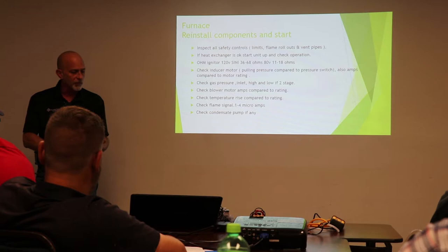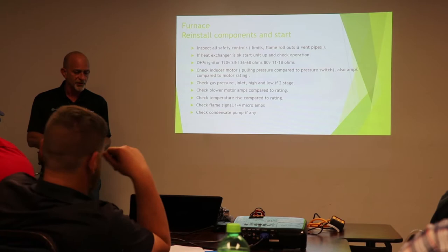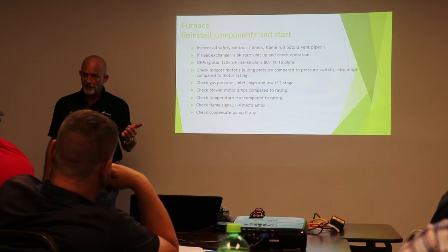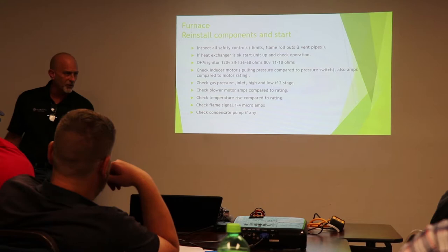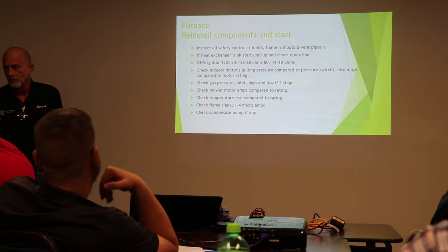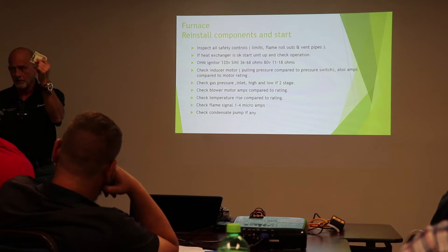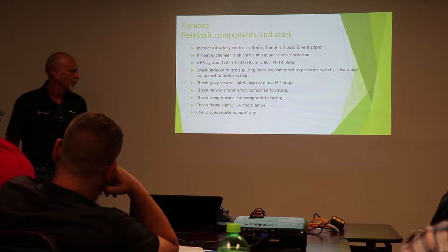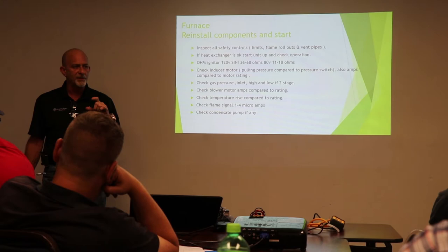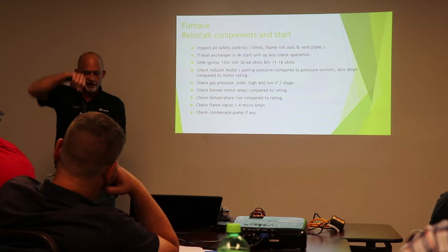No plumber's cloth. No sanding for brazing. Your sanding cloth, Scotch-Brite pad, fine steel wool, emery cloth. What if you don't have any of those with you? What's a good cleaning thing to clean a pressure switch? Hopefully everybody in here has got it in their pocket. Good old dollar bill works just fine. Clean a flame rod. I've seen floating around, I'm going to see if I can bring them in. They make a little keychain. It's about this long, and it's got little fine wires in there to clean it.